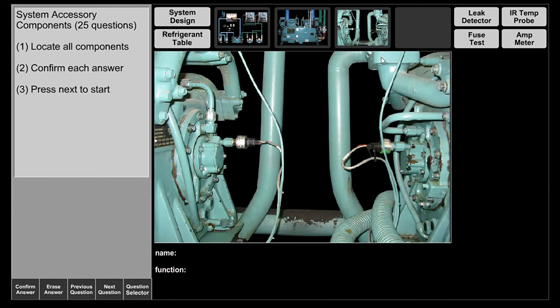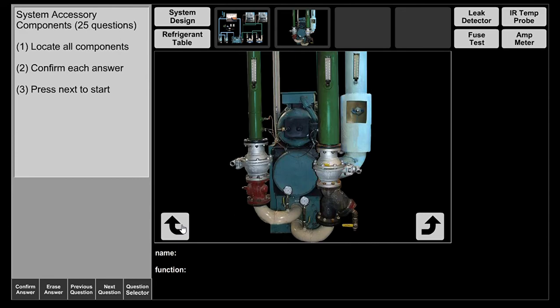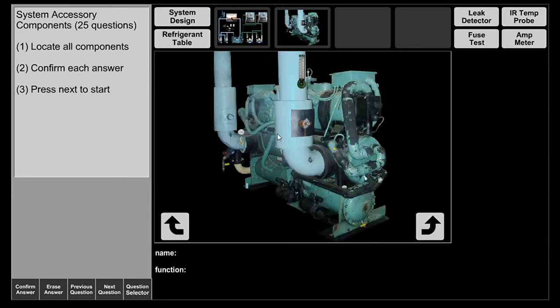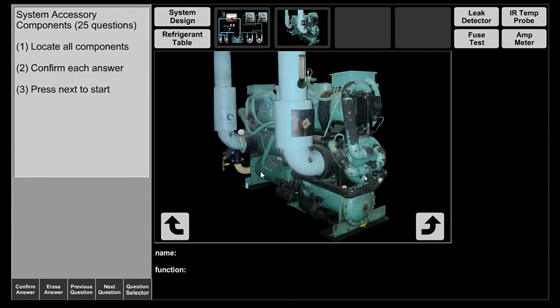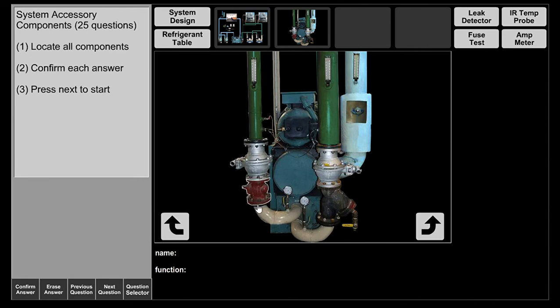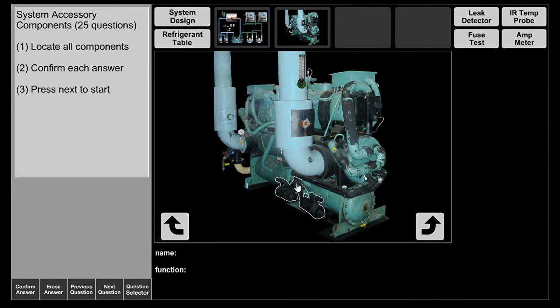Now let's move to the back of the chiller. The high pressure, high temperature superheated vapor travels into the condenser. Like the evaporator, the refrigerant is in the shell and the condenser water flows through tubes back and forth inside. Condenser water comes in at 75 degrees through a strainer, picks up all the heat from the refrigerant, and exits at 85 to 90 degrees. As a result, the high temperature, high pressure superheated vapor is condensed into a high temperature, high pressure subcooled liquid.